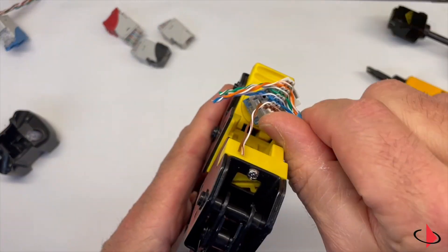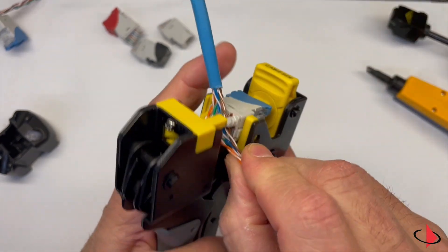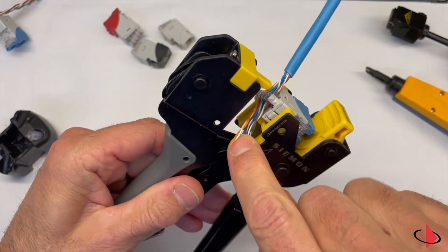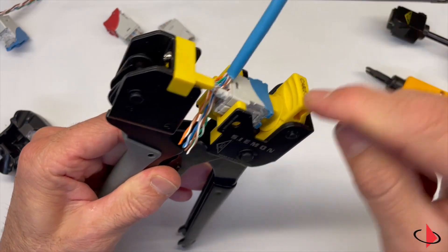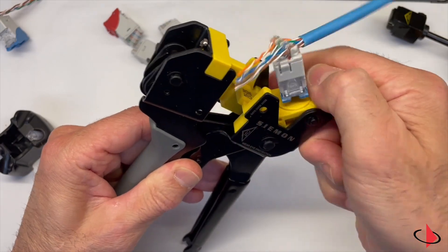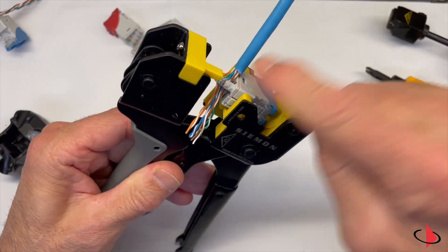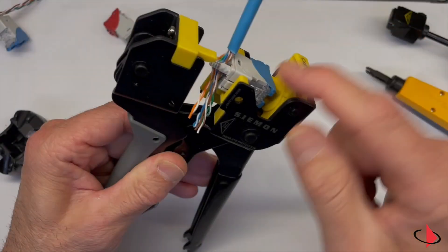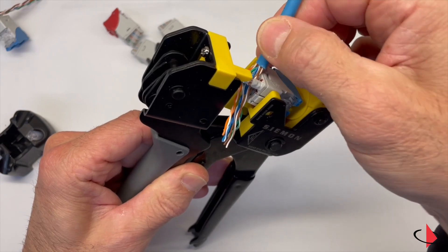When the outlet is loaded, you'll want to make sure that this is rotated such that the conductors to be trimmed are positioned properly and ideally coming out the side opening of the tool so they can drop out freely without getting caught up inside the tool. So double check that the cable side is up, cut side down with lever back to the closed position and the outlet is seated down into the base of the tool and the outlet is now ready for termination.